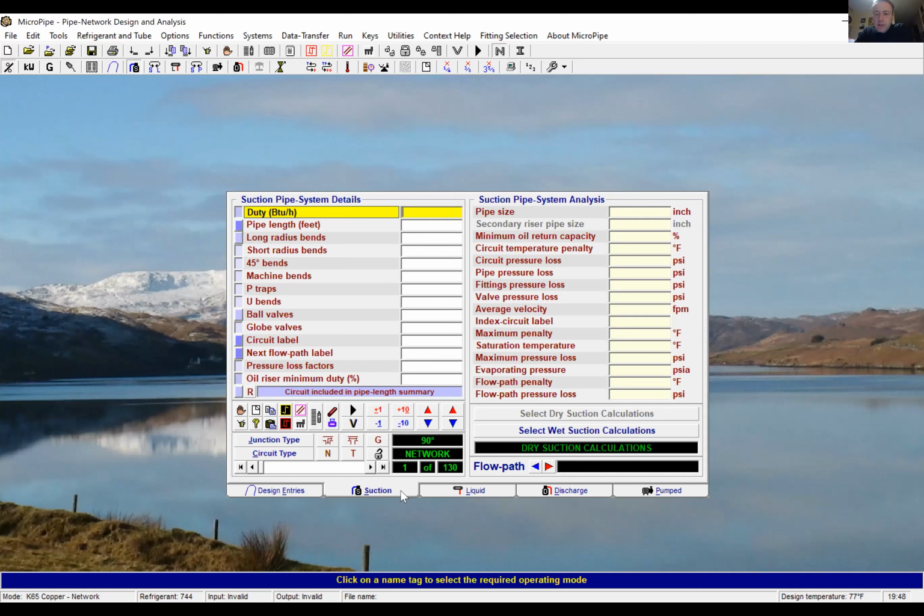But the software knows that; it's not going to undersize a liquid line to give it a high velocity. For here, in all the books I've read, it's around 1,500 feet per minute for suctions and 750 feet per minute, depending on vertical and horizontal, and for liquid it's 300, just like you said, because of liquid hammering.